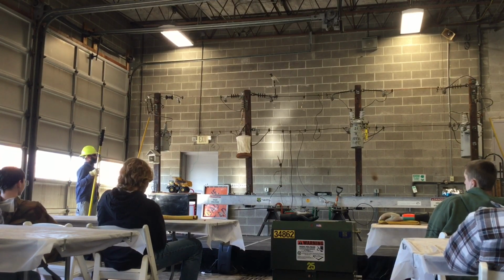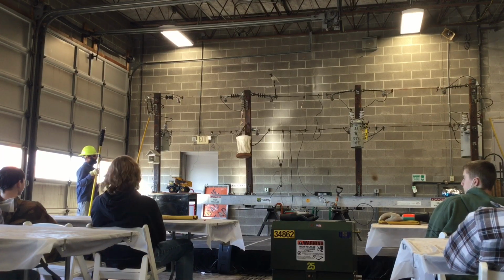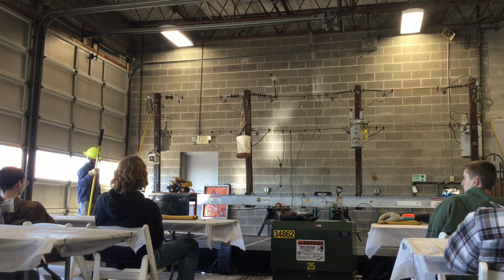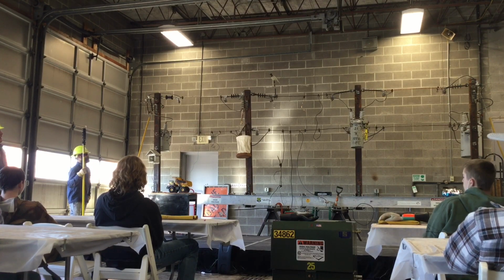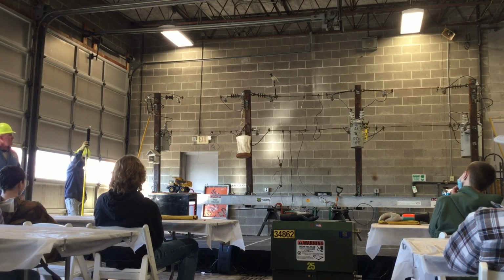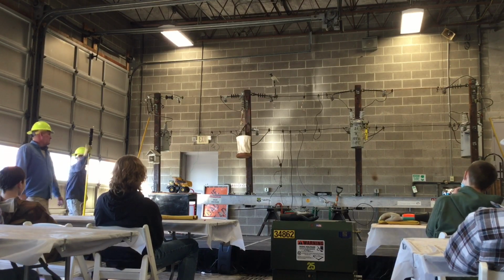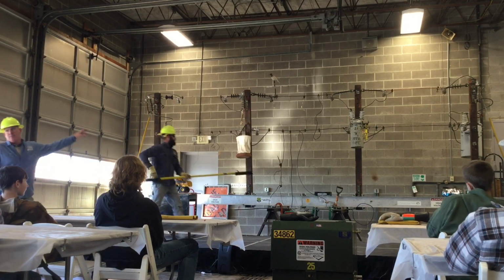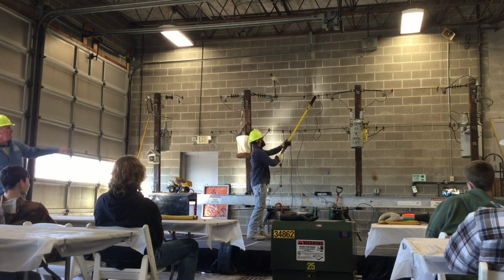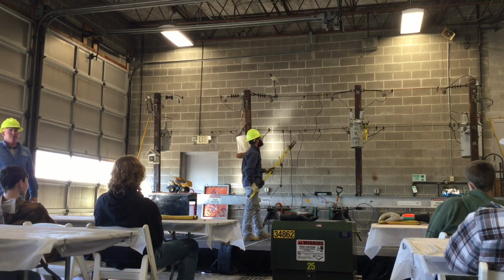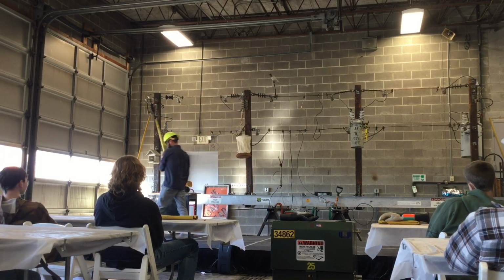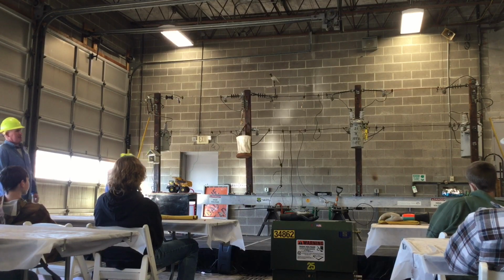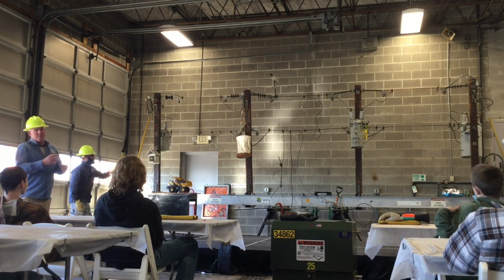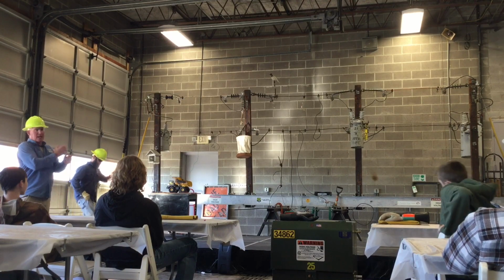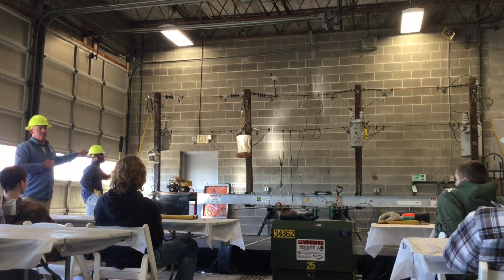You're at home, the power goes off, comes back on, it goes back off, comes back on, and it goes back off, and it's off. You guys experience that? Okay, this breaker, that's what's doing that. So Matt, we'll show him that, ground. Matt's put a fault from phase to neutral, right past this breaker. See that? So we're 7,200 to ground. So that breaker, what it does is it's sitting out there looking downstream. Like, you know, got power coming to the source side, it's looking downstream of it to see if there's any faults. That's what it does.